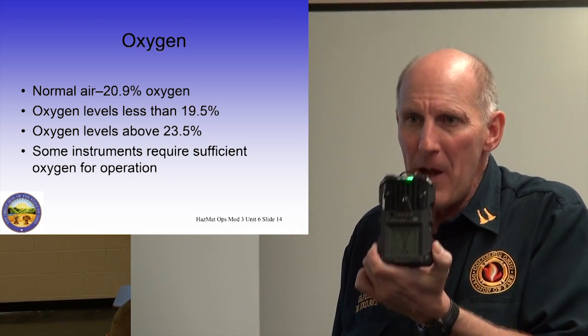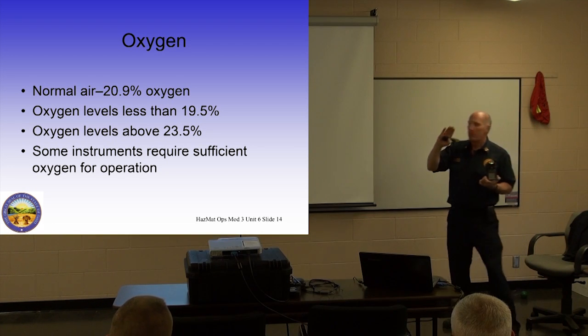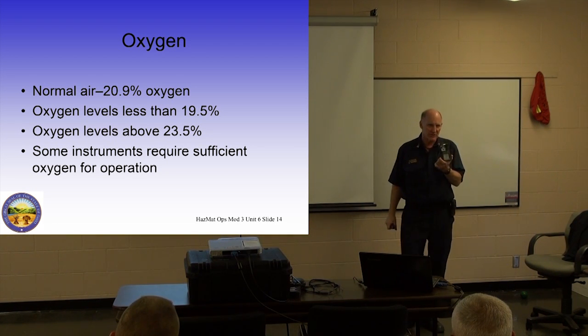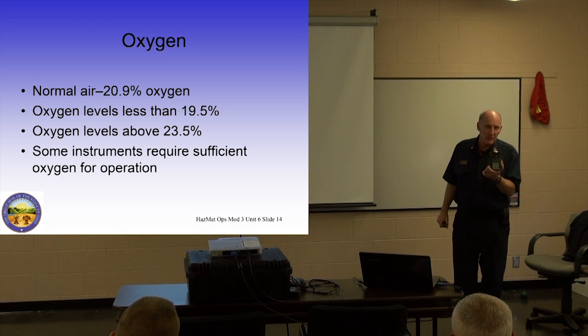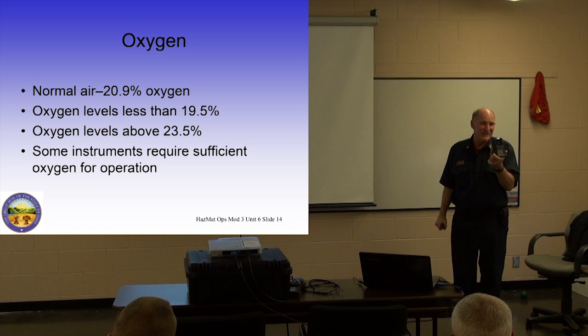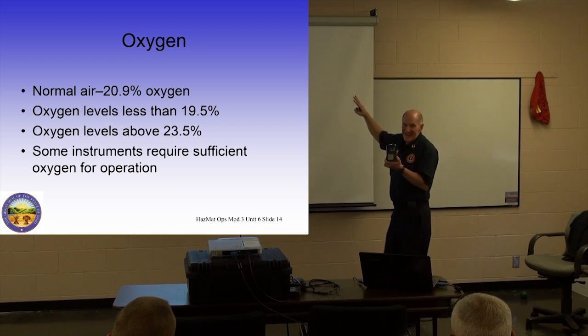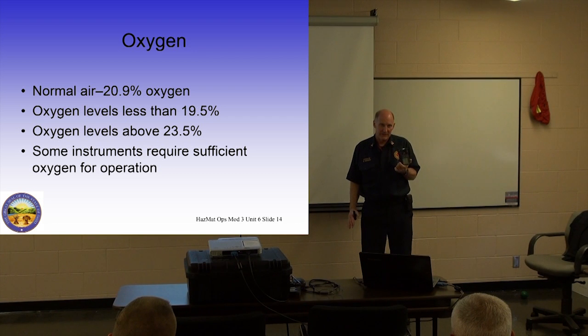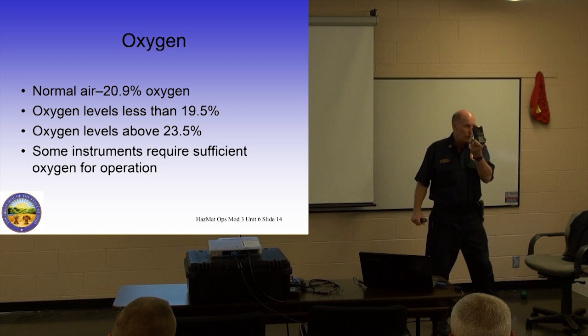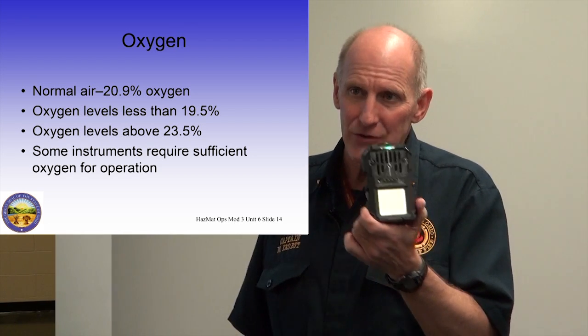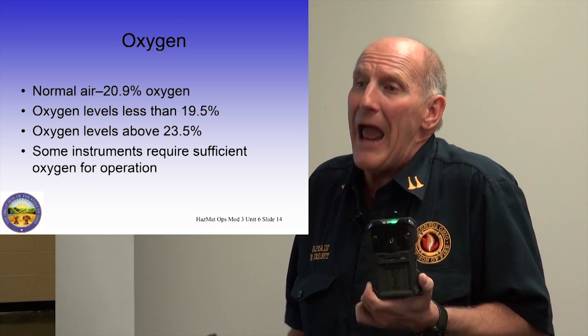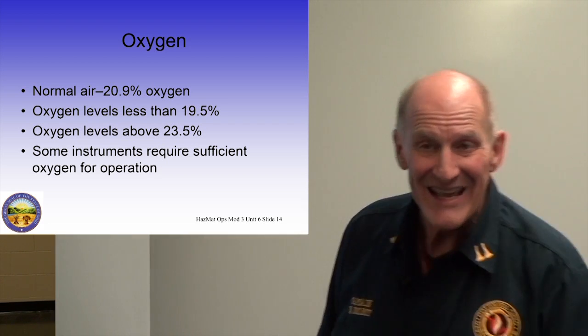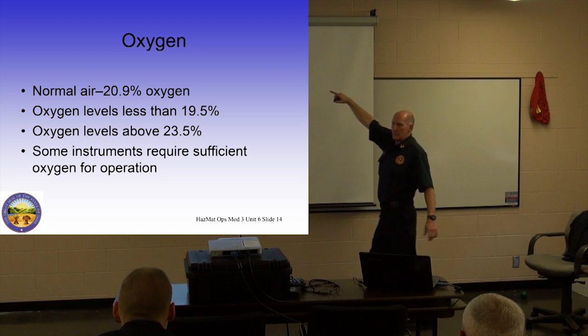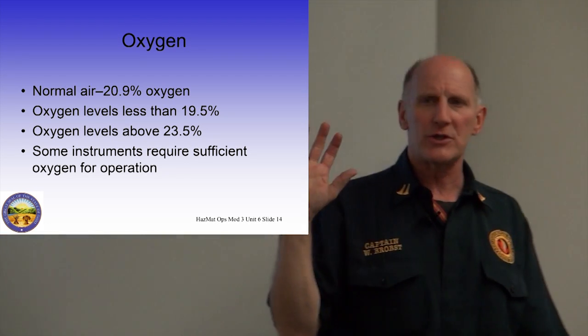But still remember this order. The first most important thing to read is the oxygen sensor. The oxygen sensor is the most critical thing to read first, because if there isn't normal O2 in the air, nothing else is accurate. I'll repeat it. If the O2 is really screwed up, you can't trust the LEL and you can't trust the other 3 sensors. They're inaccurate. Okay, specifically, we've all been taught, we've taught for years, 20.9% O2 in the air.